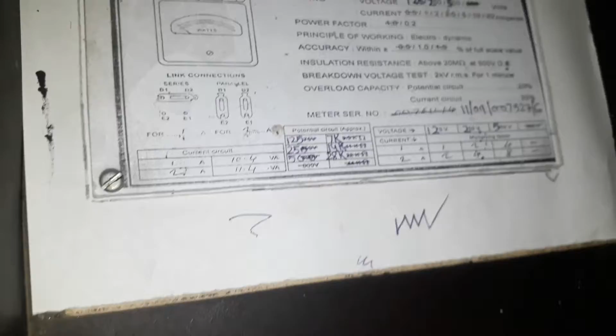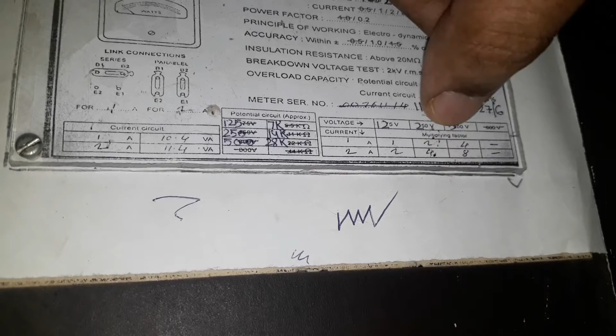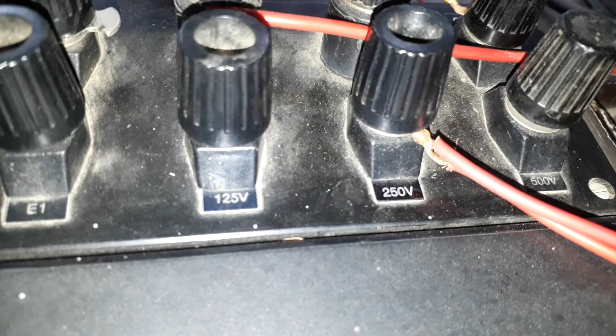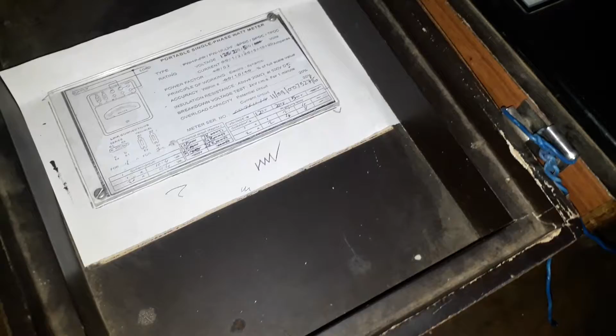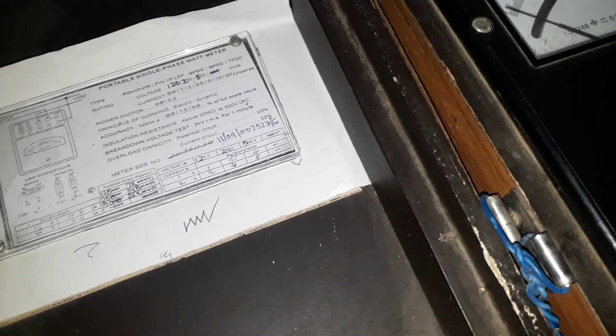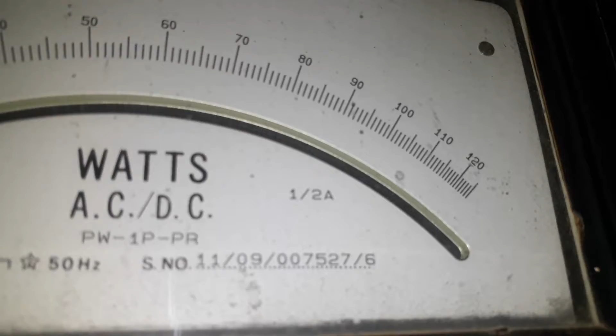We will be using this wattmeter for the 250 volt range. So in front of 1 ampere, beneath 250 volt, you see the multiplying factor written here is 2. Alternatively, we can calculate the multiplying factor of the wattmeter using the simple formula V into I over W. V is the voltage range of the wattmeter being used—here it is 250 volts—and I is the current range, 0 to 1 ampere, so 1 ampere is the current, and W is the range of the wattmeter. So from this as well you can calculate the multiplying factor.